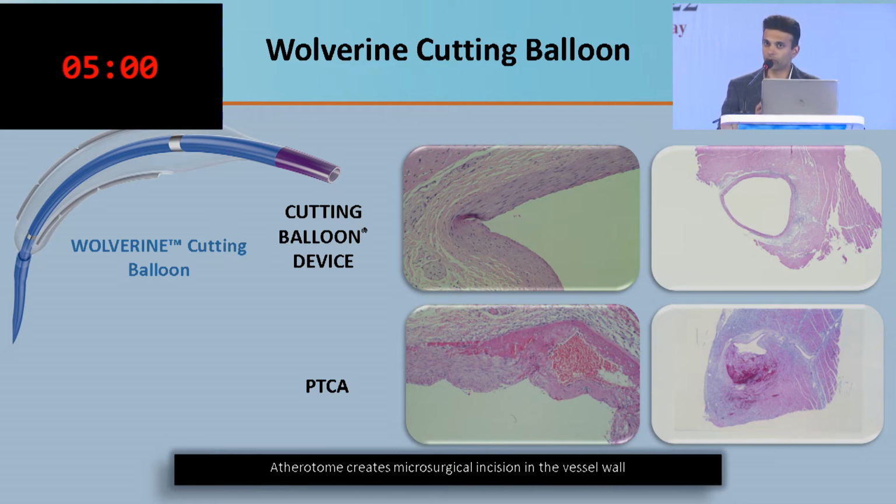So what you're doing by putting these things up to high pressures, and the iteration on the Flextome was tighter packing and the fact that the Flextome atherotomes were squares. These are triangles. When you impart force on a triangular atherotome, a smaller unit, you're imparting more force per unit area. So this is to make a crack, okay? This device is to make a crack. That's what you're really trying to achieve.